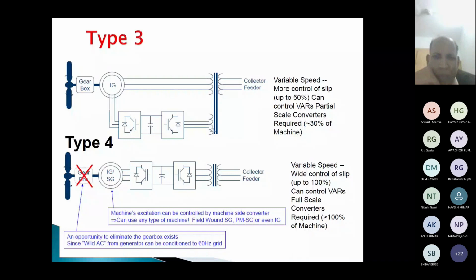Talking about the type 4, which can be based on the induction generator or synchronous generator. Synchronous generator is more popular. Here it again uses power electronic converters. And here, of course, we are only drawing the power from the stator terminals. So the converter rating is the same as that of the generator rating, like converter rating is 100%. However, with this design, the control of frequency, control of reactive power, or control of slip is up to 100%. So there is significant flexibility. Of course, the cost of the generator increases, but we are able to extract more power from the wind turbine.